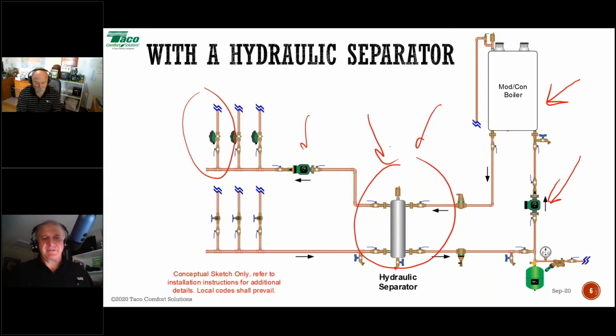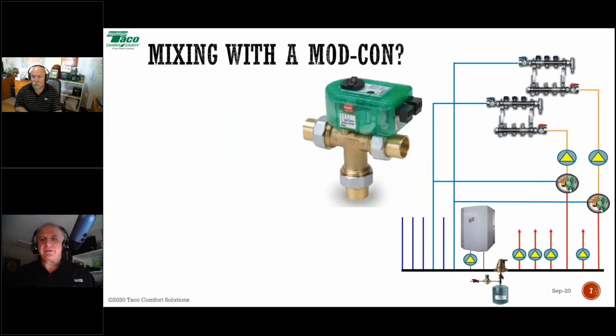We're going to get into buffer tanks at the end, because buffer tanks come into play when your smallest zone is smaller than the lowest firing rate of your boiler. We want to do everything we can in those instances to prevent short cycling with that boiler. So we'll talk about that at the very end.